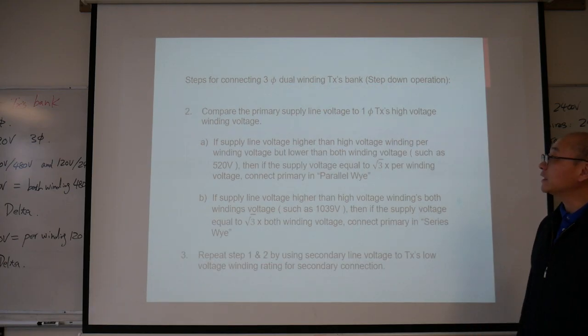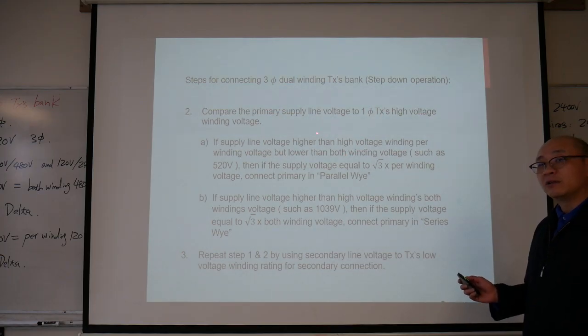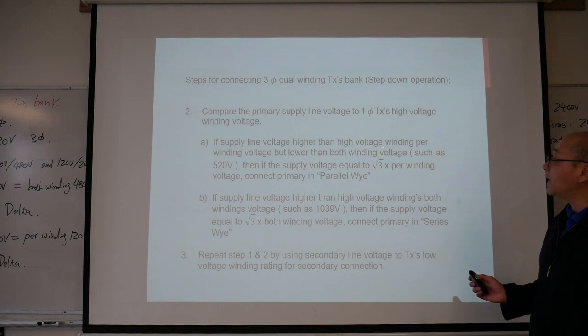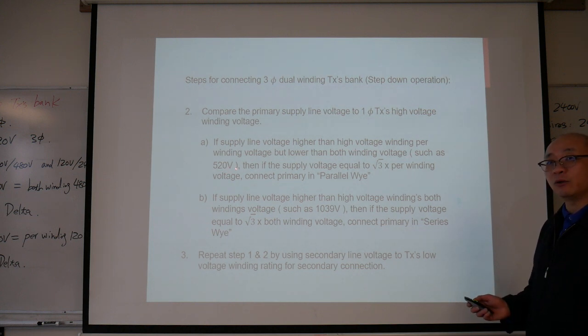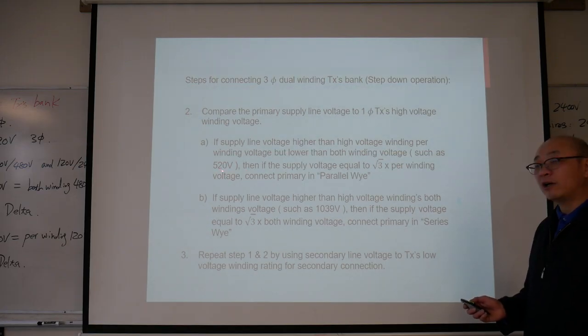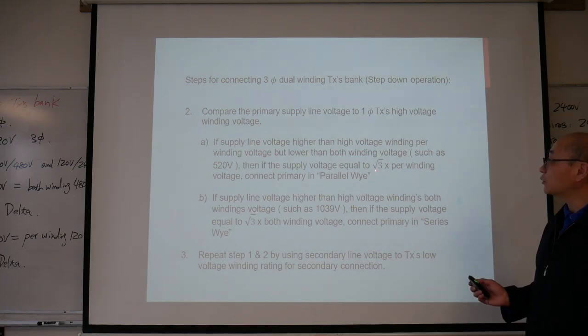If your supply voltage is not equal to either of those two numbers, you go to the second step. You compare the supply voltage to see if it's higher than 300 volts, lower than 600 volts, or higher than 600 volts. Let's say the sample is 520 volts. It's not equal to 300 volt, not equal to 600 volt, but it's higher than 300 and lower than 600. So you check if root 3 times 300 gives you 520. Yes, it does, so you connect your primary in parallel Y. Otherwise, if your supply voltage is 1039 volts, which is higher than 600 and equal to root 3 times 600, then you connect your primary in series Y.